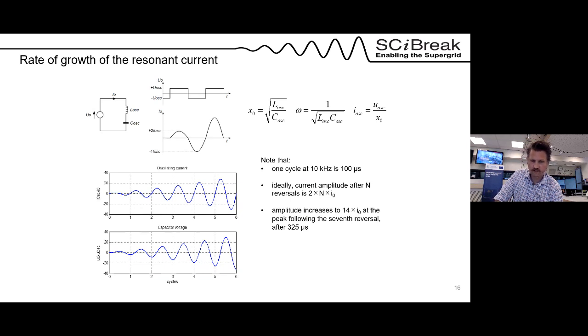And this means that regardless of what line current we would like to interrupt, we will have a resonant current that fairly closely matches that line current. And we will have a zero current crossing in the VI with very little overshoot in the resonant circuit current. And this is beneficial for the interruption process. The resonant frequency used is typically around 10 kilohertz. So even if we aim for very fast current interruption, we still have time for quite many resonant frequency periods within that short interruption process.